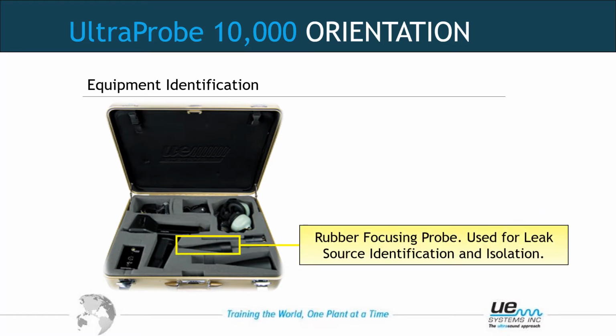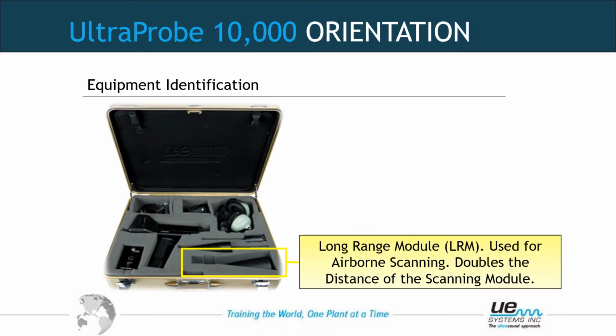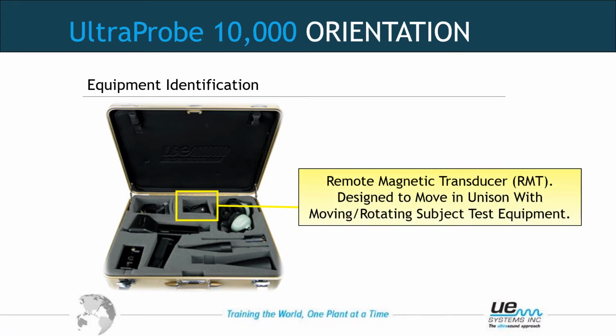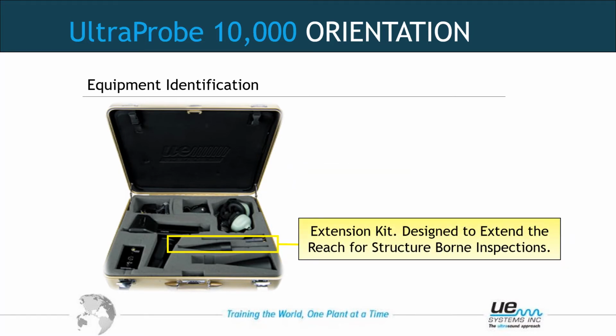The rubber focusing probe used for leak source identification and isolation to pinpoint areas of interest, such as a leak, or as extra shielding over the stethoscope module in noisy ultrasonic environments. The long-range module, an airborne module with a 10-degree field of view that doubles the distance of the normal scanning module. The remote magnetic transducer, which is designed to use on vibrating equipment or rotating equipment, something that is moving too much to use the stethoscope module, 27-pound pull with a stretch cable. And the extension kit, designed to extend the reach for the structure-borne inspections. 3 aluminum rods that screw into the base module of the stethoscope module.